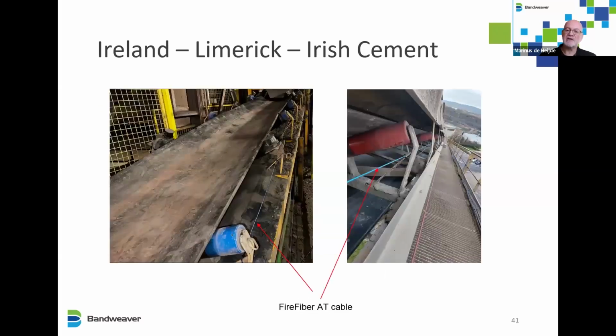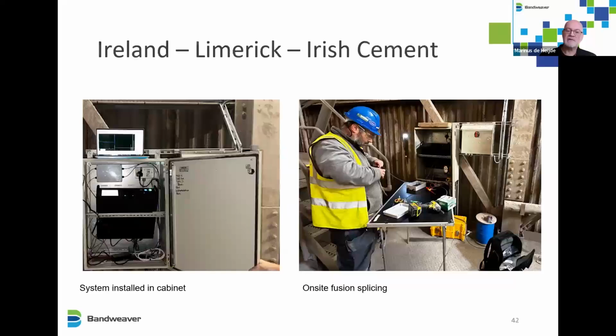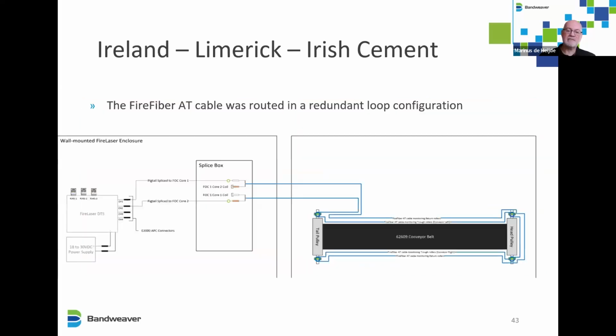So here's where you can see a couple of the pictures of the installation itself. So it was installed in a cabinet, which was IP rated because it was quite a dirty environment. And we hired a local contractor to do some of the fusion splicing. Fusion splicing is needed when you install the unit, but also when you have repairs to the cable. It's basically you splice the cable back together. So it was routed in a redundant loop configuration, as we discussed earlier on. It then went to a splice box, and from the splice box, into the DTS unit itself.